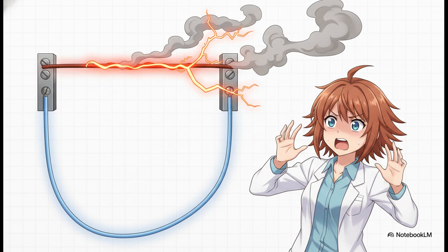Here's the actual physics behind the code. Electricity is lazy. It takes the path of least resistance. If one wire is even slightly shorter than the other, it has lower resistance. Therefore, the shorter wire is going to hog all the current, exceed its ampacity, and start to melt. This is exactly why you have to ensure those lengths are perfectly equal.